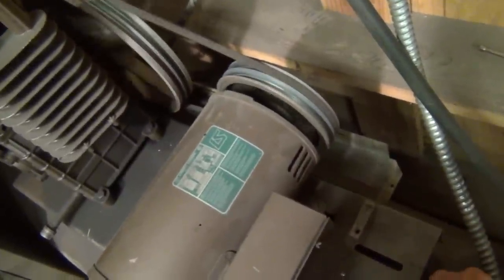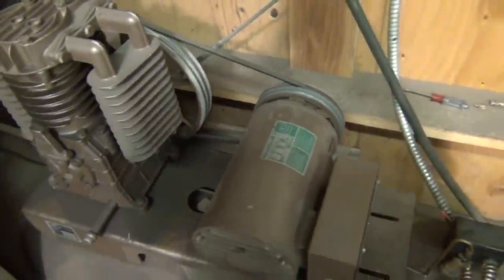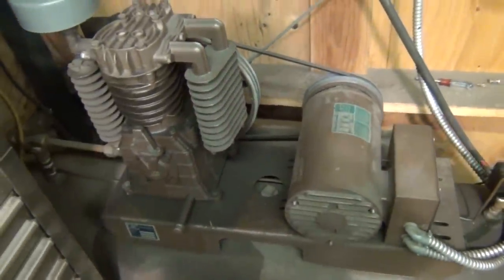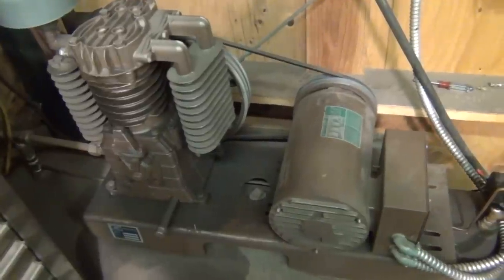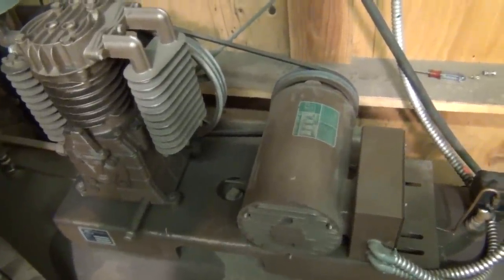Now that we know it turns over easy by hand, I'm going to flip the pressure switch on and just see what we get here. Alright, so as you can see the motor had a hard time starting up there. It turned a couple of revolutions but definitely didn't have enough torque to come up to speed.